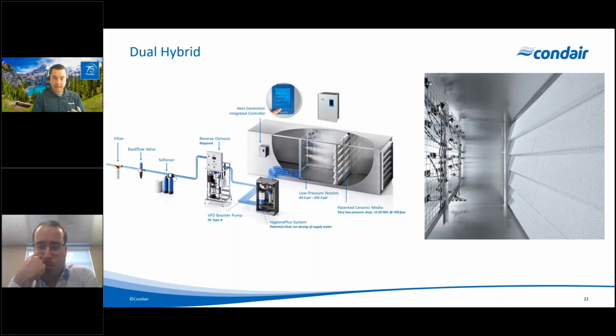And then downstream, instead of a traditional glass fiber or polyester media we would have on the ME system, we have a fairly unique ceramic media, which is a porous tile that you can see here in the photo that is effectively good for the life of the unit, but that acts as a droplet separator and post evaporator as well. Now, because of the design of this with two modes of evaporation, the lower pressure and the ceramic media downstream, we can actually install that in a 24 to 36 inch section, with some requirements for clearances upstream and downstream. But the big difference there between the high pressure system is we're able to shrink that absorption distance down from 5 feet down to 24 to 36 inches.